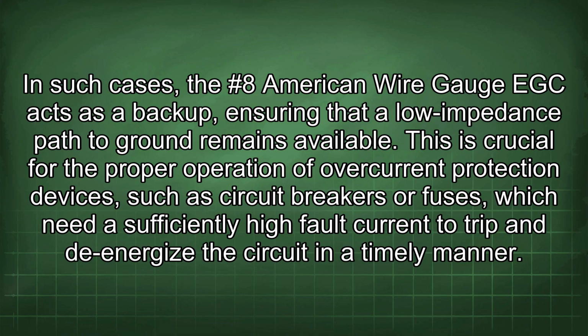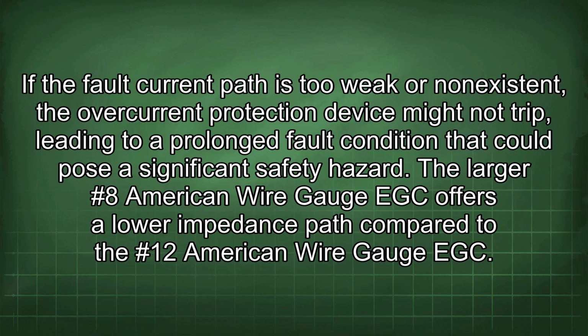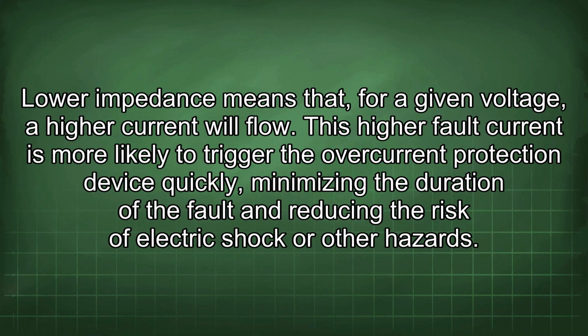In such cases, the #8 American wire gauge EGC acts as a backup, ensuring that a low impedance path to ground remains available. This is crucial for the proper operation of overcurrent protection devices, such as circuit breakers or fuses, which need a sufficiently high fault current to trip and de-energize the circuit in a timely manner. If the fault current path is too weak or non-existent, the overcurrent protection device might not trip, leading to a prolonged fault condition that could pose a significant safety hazard. The larger #8 EGC offers a lower impedance path compared to the #12 EGC. Lower impedance means that for a given voltage, a higher current will flow. This higher fault current is more likely to trigger the overcurrent protection device quickly, minimizing the duration of the fault and reducing the risk of electric shock or other hazards.